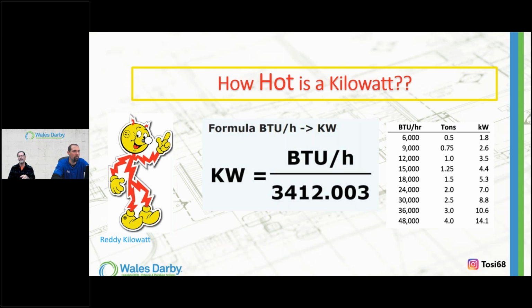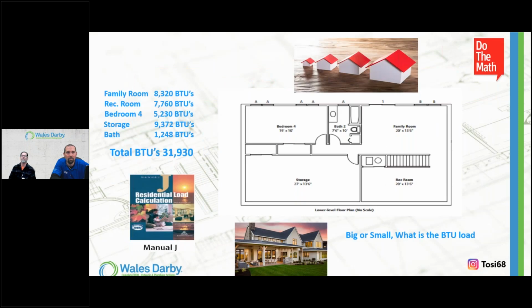There's nothing about temperature here. We determine what temperature is needed based off of our emitter's output, how much surface area, okay? So therefore it goes back to, I need to deliver X amount of BTUs, or maybe in terms of kilowatts. So if we did a load calc, big or small, what is the load? We have the ability to do programming, we have Manual J's, we have a lot of different information that we can get involved with and do room by room, zone by zone. And then we do the whole space, the whole house. That's how we determine at best judgment what our source would be.